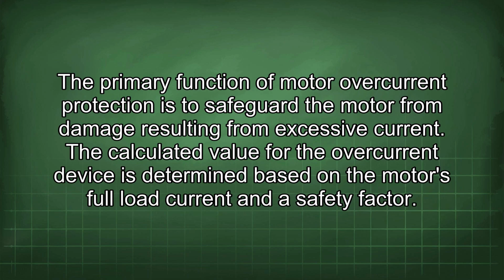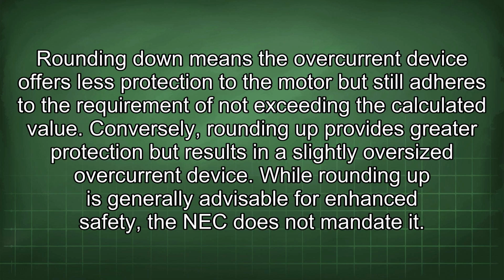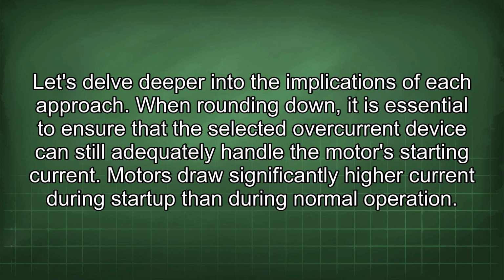The primary function of motor overcurrent protection is to safeguard the motor from damage resulting from excessive current. The calculated value for the overcurrent device is determined based on the motor's full load current and a safety factor. Rounding down means the overcurrent device offers less protection to the motor but still adheres to the requirement of not exceeding the calculated value. Conversely, rounding up provides greater protection but results in a slightly oversized overcurrent device. While rounding up is generally advisable for enhanced safety, the NEC does not mandate it. Let's delve deeper into the implications of each approach.